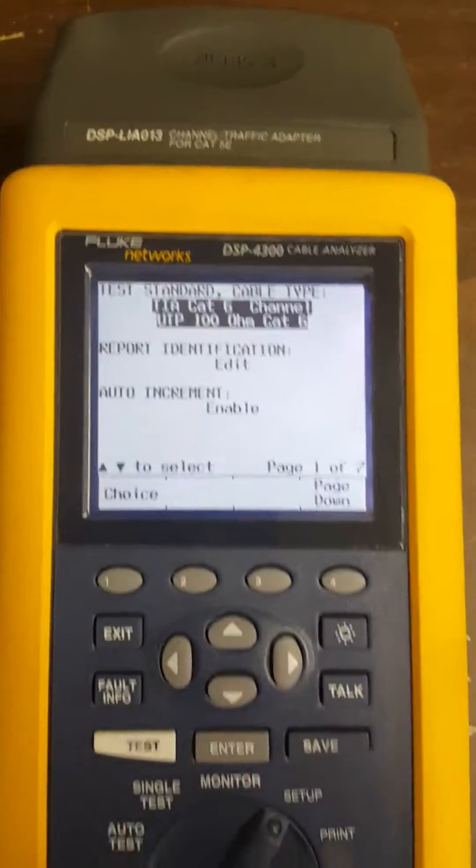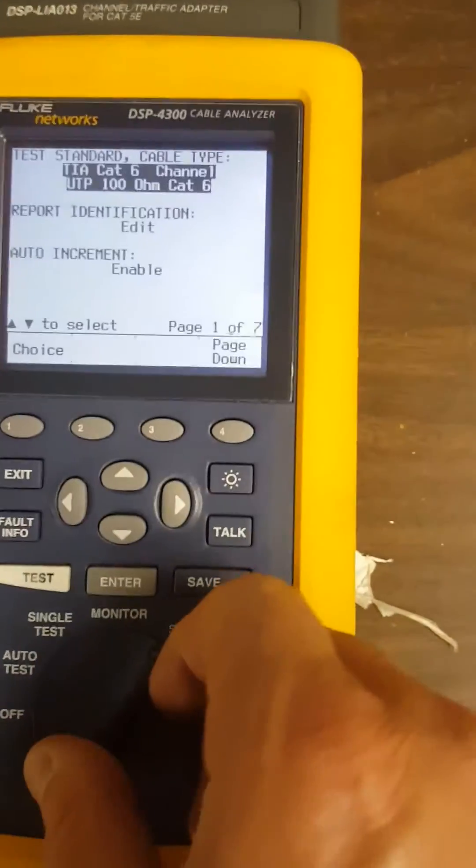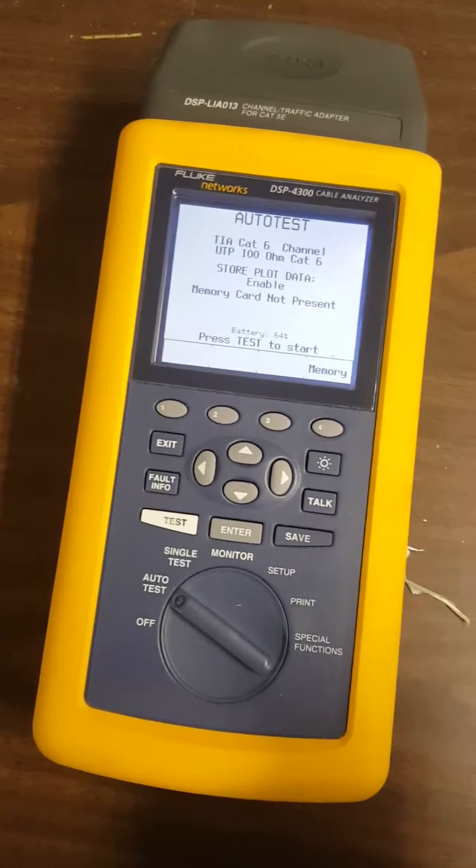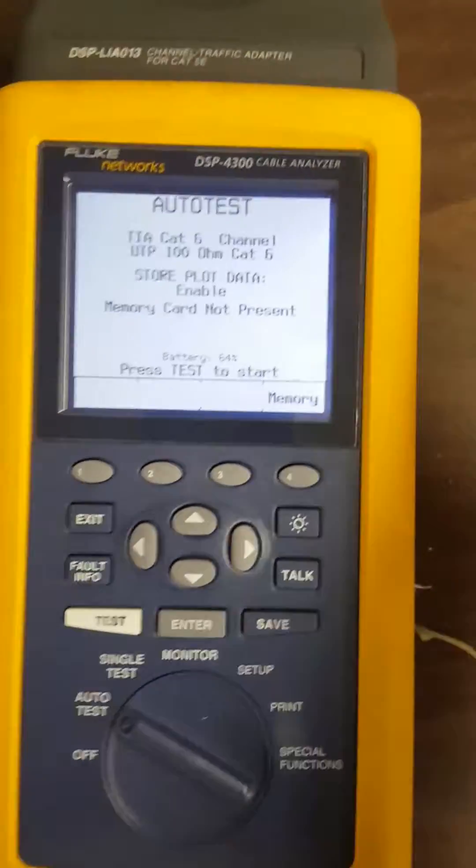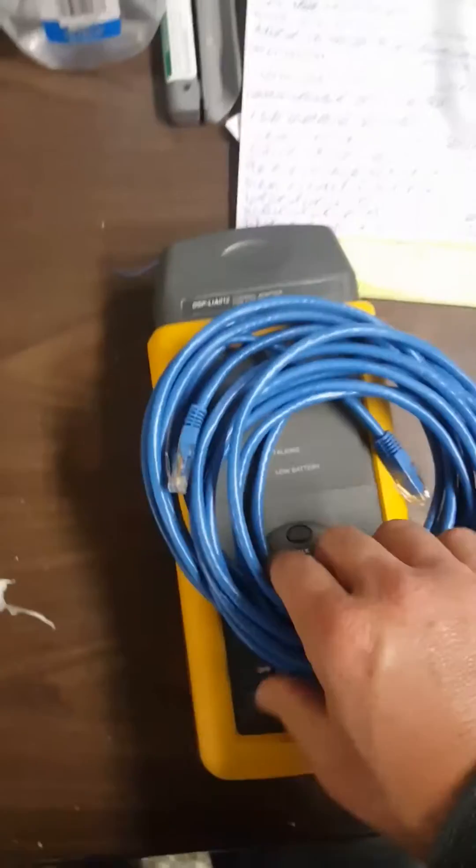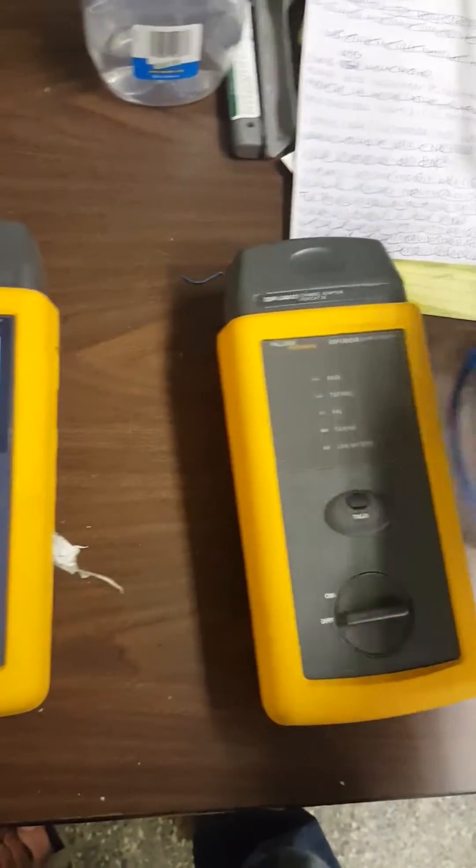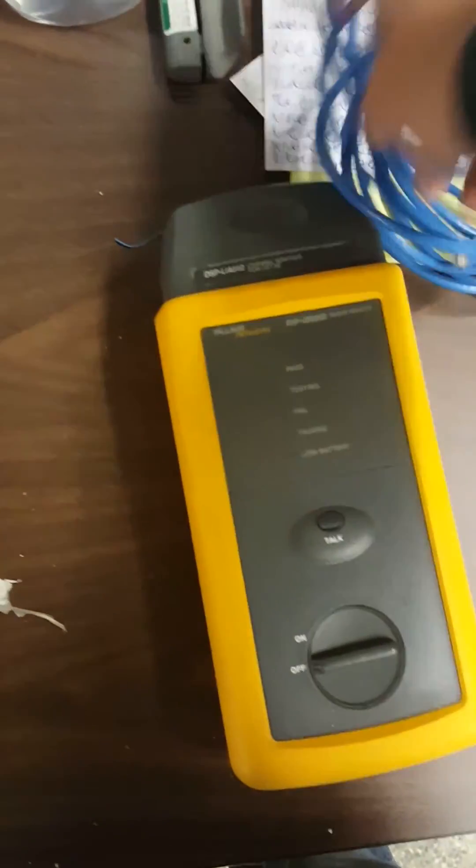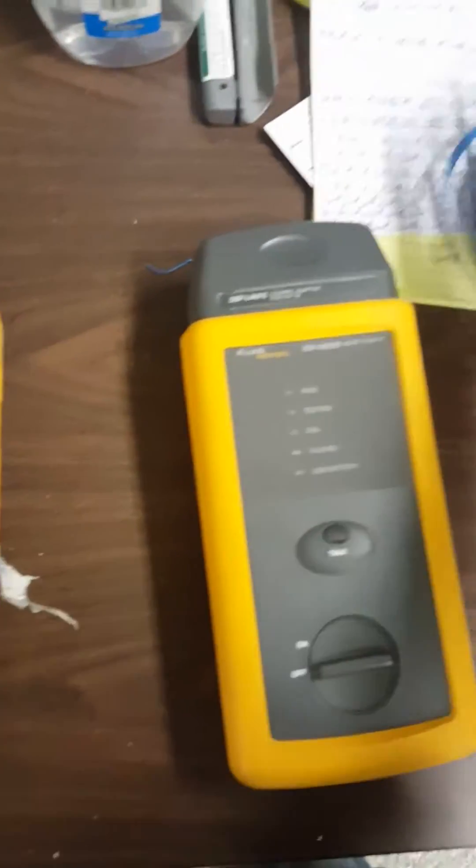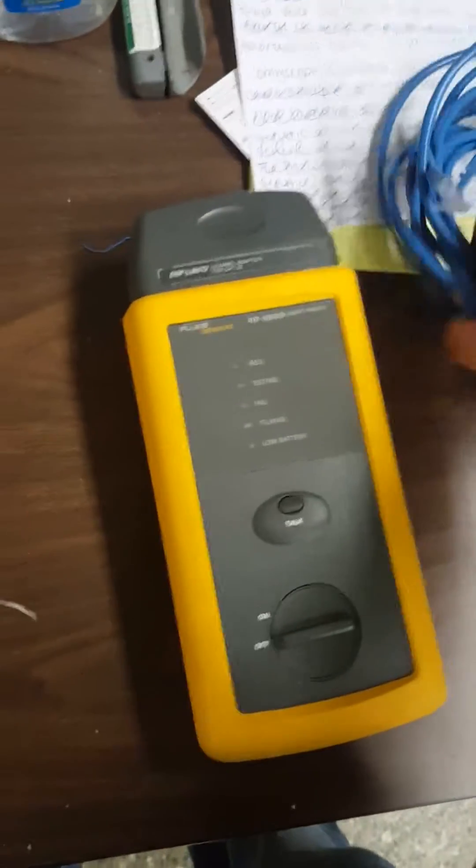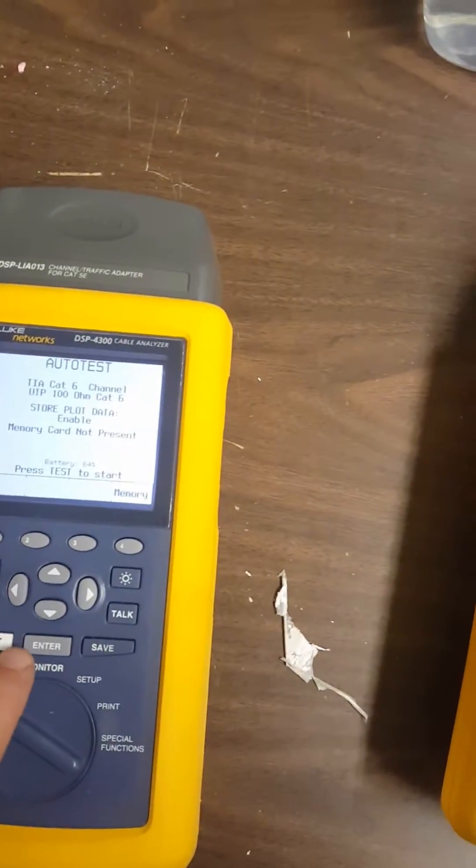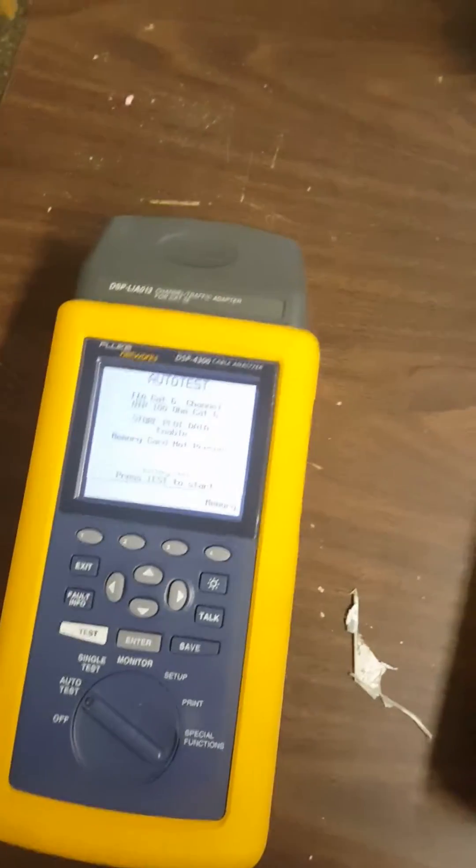And we're done. Okay, so this part's set up. Then you go to single test, and then from here you'd actually have, let's see here, these... you want to use one of these. These are two patch cords, one on each side. One will plug in here to the patch panel, the other end will plug in here to the jack. These are 10 foot patch cables. They need to be used. It needs to be over 10 feet or more of patch cord in order for this to test. And then you just hit test, and that's it.